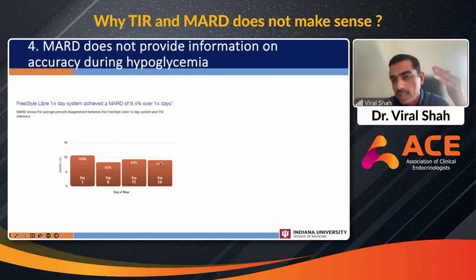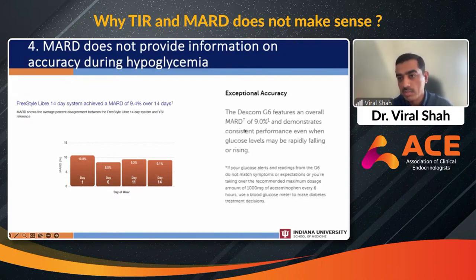So the MARD says 9.4. Now it might say something different in India—I don't know, because the marketing in India versus the US may be slightly different. And then I'm comparing the Dexcom here, Dexcom G6, which has a MARD of 9.0. 9.4 versus 9.0 is not very different, it's only 0.4. So if you think about MARD, these sensors are highly comparable.